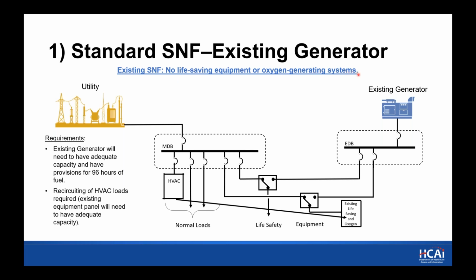There'll be a survey that you'll need to take to determine that, but if that's the case, then you'll see that we have a standard configuration with an existing generator and 2 transfer switches, one for life safety and one for equipment. And in a normal configuration, most of the time we're going to see in the SNFs that the HVAC, the cooling equipment, is going to be connected to normal power. So if the generator has adequate capacity, distribution has adequate capacity, you could transfer those HVAC loads to the equipment branch, and then you would have successfully backed up your cooling requirements.